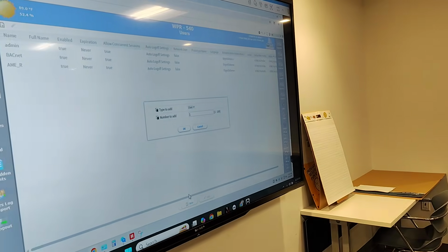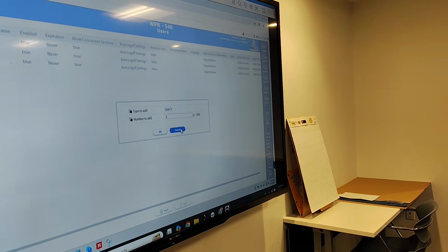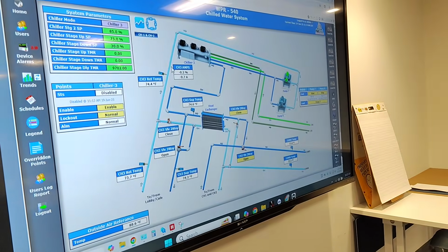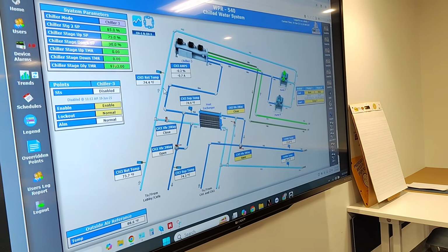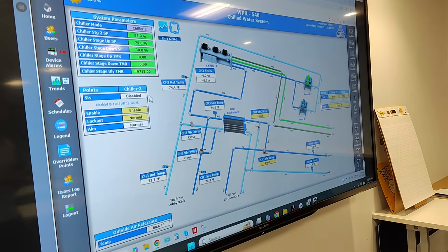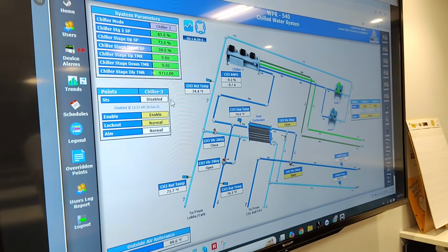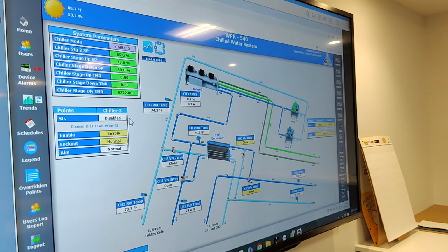We need this chiller. It also affects this room. So now, can you just see if the chiller water temperature is better or not? It just started. Let's see what it is, and then let's look in 10 minutes. Look at the temperature that's entering the heat exchanger. That seems to be the best number off your chart right there. It would come to 74. So let me just look at that.